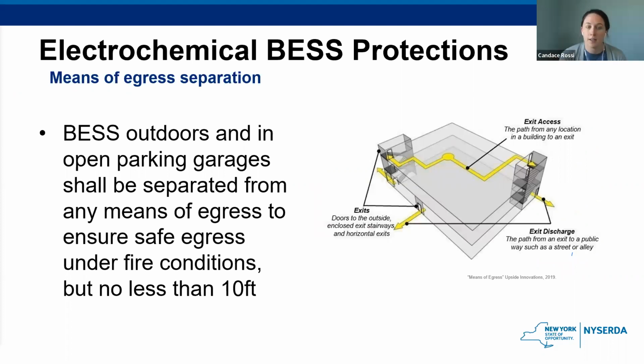So here we have the means of egress. So egress from an open parking garage is very important, and these systems should not be within 10 feet of those pathways. A code official can approve smaller distances also based on large-scale fire testing. But you want to make sure a continuous and clear path from any occupied portion of a building to a public way, such as an outdoor sidewalk. So a means of egress consists of 3 parts: the exit access, the exit itself, so doors to the outside, and the exit discharge, the route from the exit to the public way. So this requirement for outdoors and open parking lots, you want to make sure there is a means of egress if there is an issue.